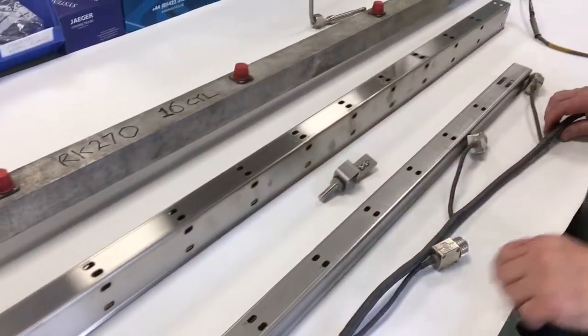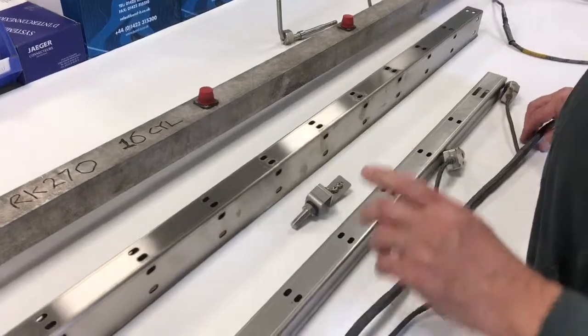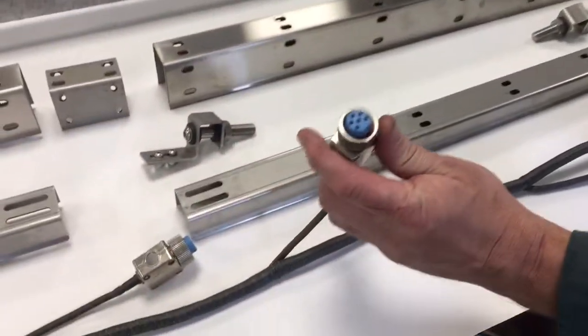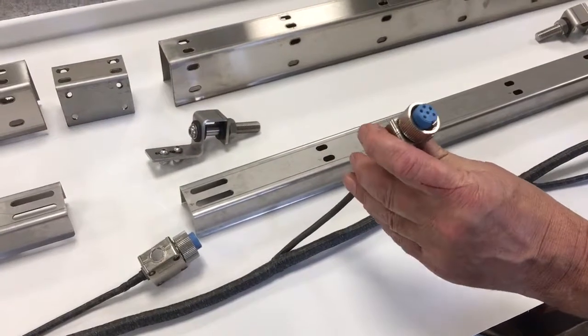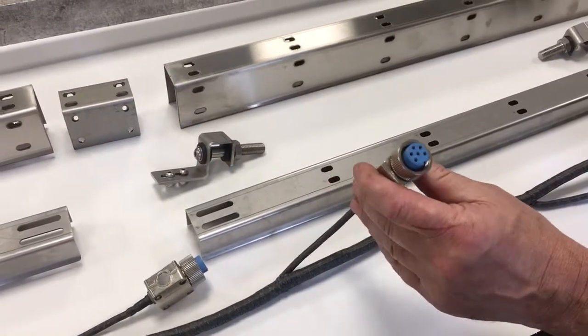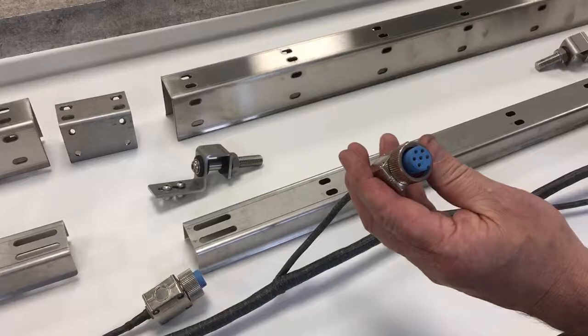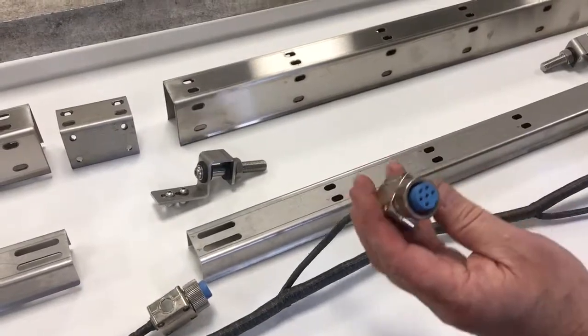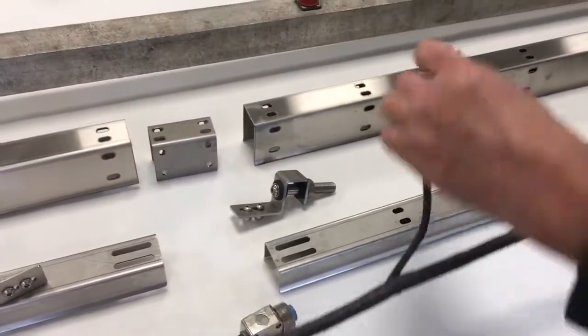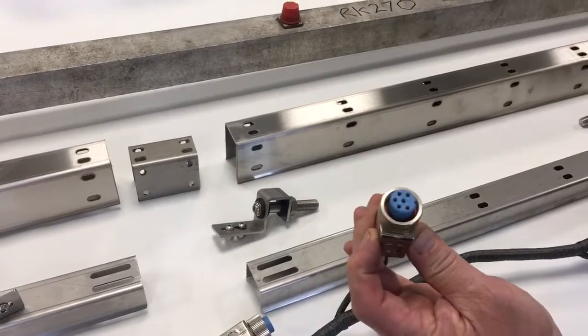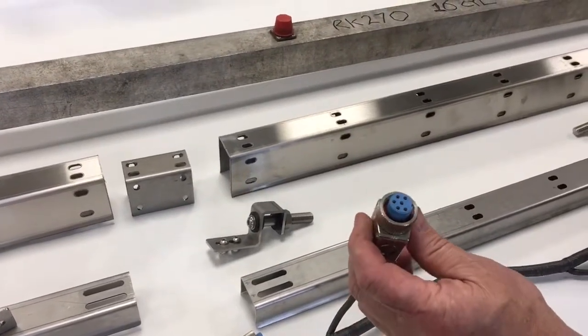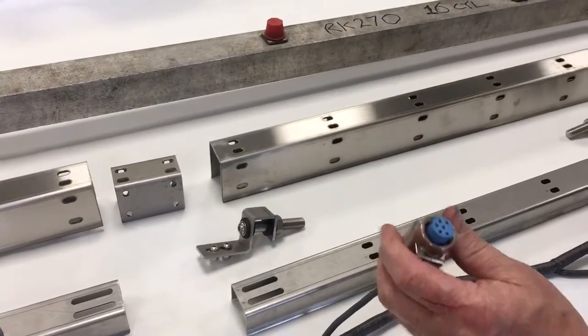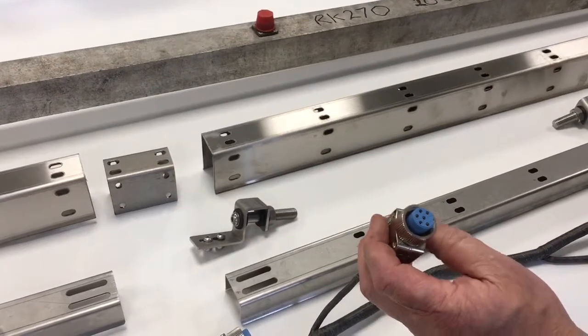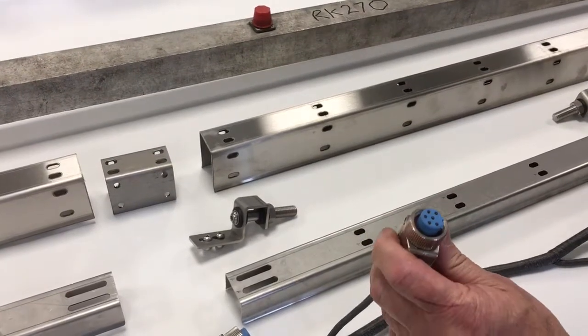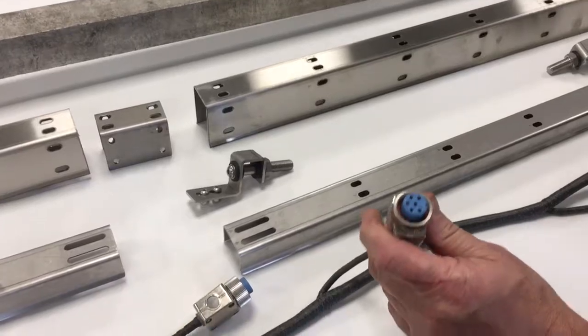Main differences between the flexible harness and the solid harness are this is a powered circuit. We convert all signals to 4 to 20 milliamps, and all the connectors are female, so this avoids any risk of the pins shorting out and causing problems to the power supply. It is possible to do things using the existing connectors, but then you need to have protection circuits for your power supply.